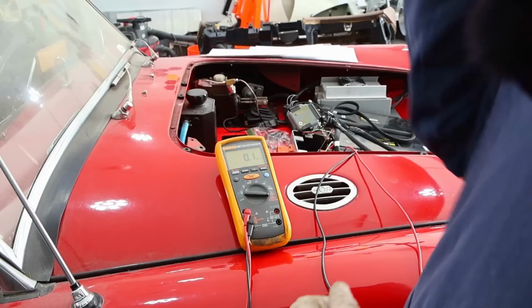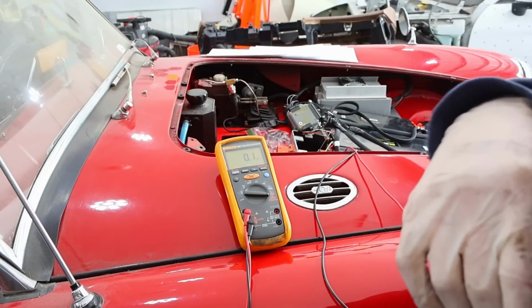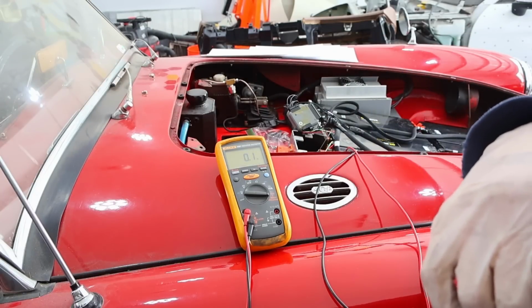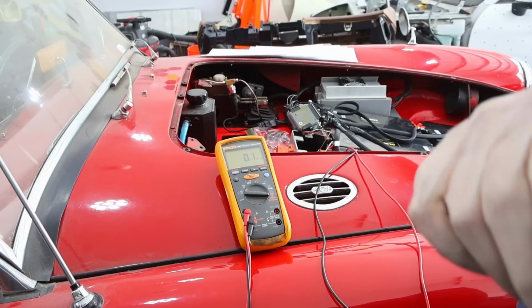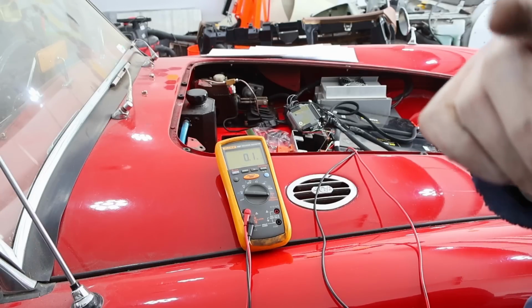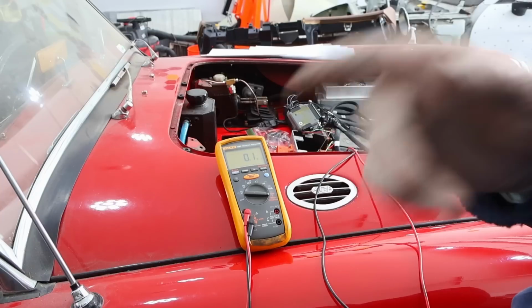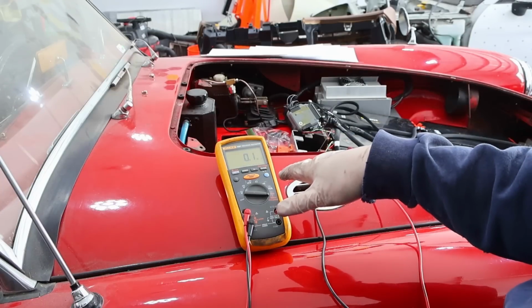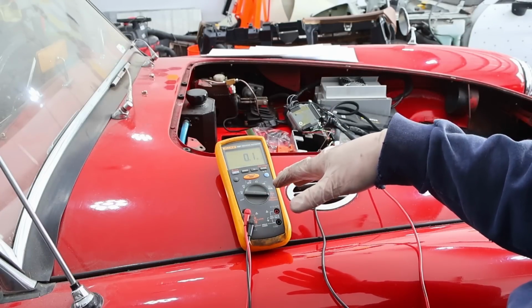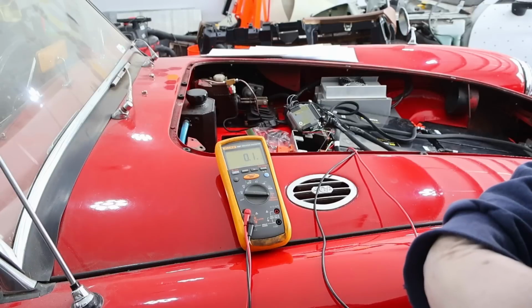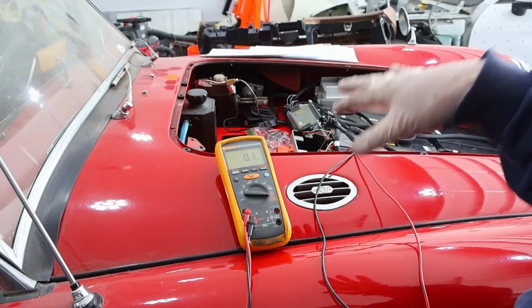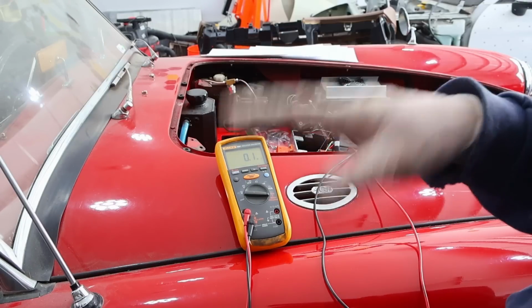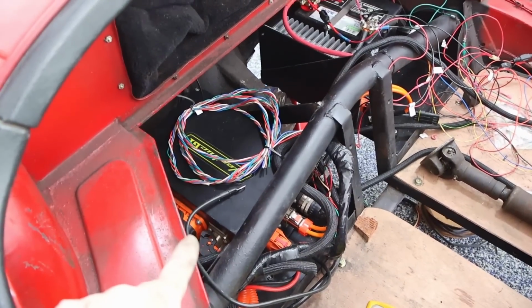On the BMS screen it shows 20%, but we want to be at 100%. What I'm going to show you is going to the high voltage junction box and unplugging things, which gives us back 1 or 2 giga ohms. So it seems like the problem isn't the wiring or cabling, it's something inside the high voltage junction box.